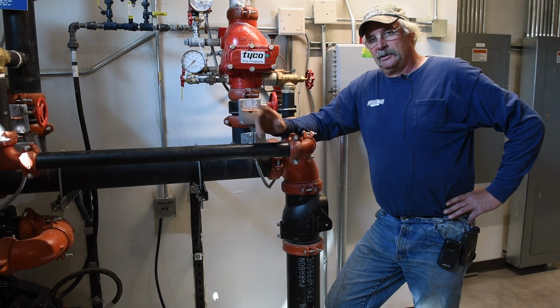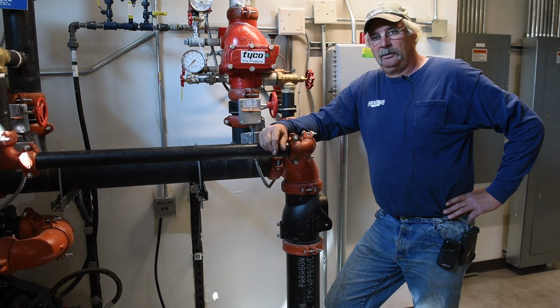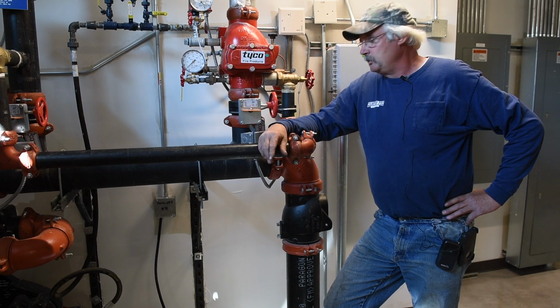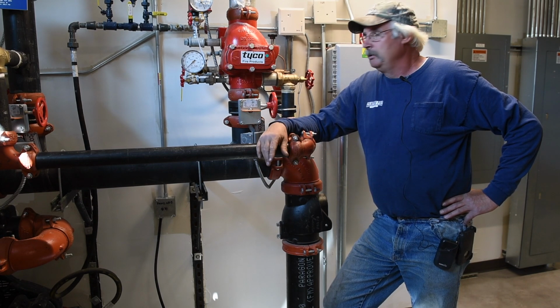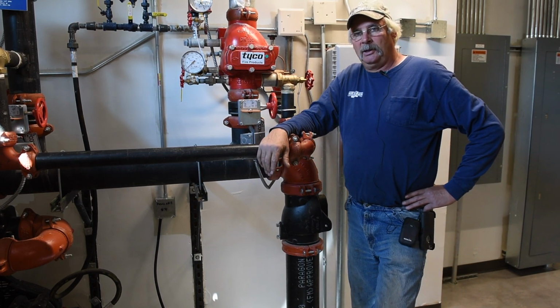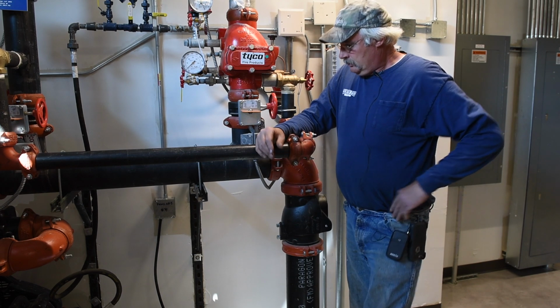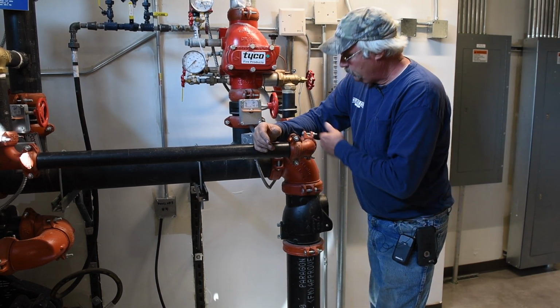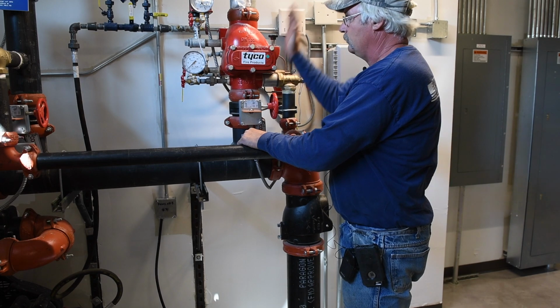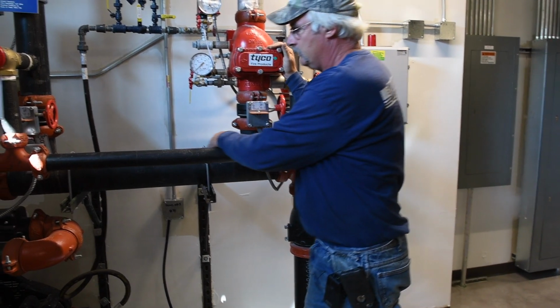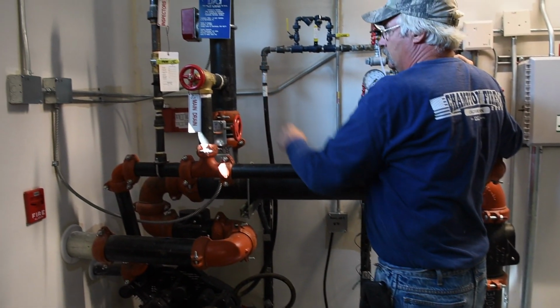And there's 2 valves on the right-hand side, and we'll take Ben up there and make sure we open the doors and show them to you. Very important to drain all the water. The care and maintenance is by the owner. So basically the underground comes up, we have a header, we have a dry system which takes care of the attic. It continues on, we have a wet system.